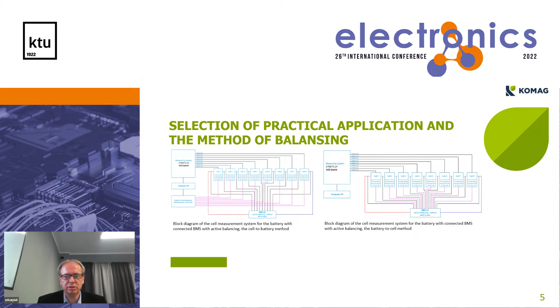The tests were carried out for headway lithium-iron-phosphate cells. Due to the need to control the temperature of each cell during BMS operation, it was necessary to determine the location of the measuring point with the highest test temperature. The test results indicate that the highest test temperature occurs at the positive pole of the cell, which is shown in the diagram.